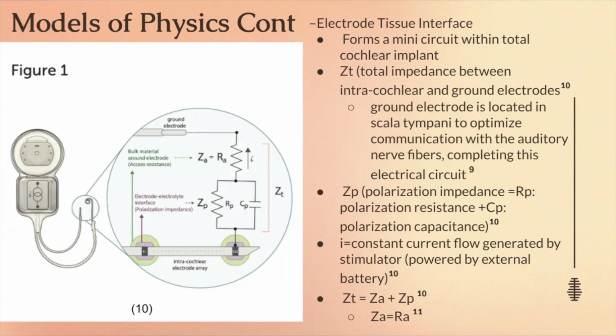Here, ZT, one component, is the total impedance between the intracochlear and ground electrode, and the ground electrode is located in the scala tympani to optimize communication with auditory nerve fibers. ZP is the polarization impedance, which is equal to the polarization resistance RP plus CP, the polarization capacitance, RP representing the restriction of charge transfer in the electrode-electrolyte interface. CP is the polarization capacitance, also related to the electrolyte-electrode interface. Both are important in protecting the electrode when voltage is applied. And I is the constant current flow generated by an external battery.